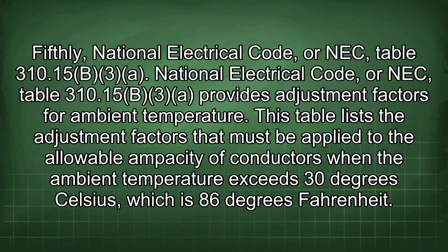Fifthly, National Electrical Code, or NEC, Table 310.15(B)(3)(a). National Electrical Code, or NEC, Table 310.15(B)(3)(a) provides adjustment factors for ambient temperature. This table lists the adjustment factors that must be applied to the allowable ampacity of conductors when the ambient temperature exceeds 30 degrees Celsius, which is 86 degrees Fahrenheit.